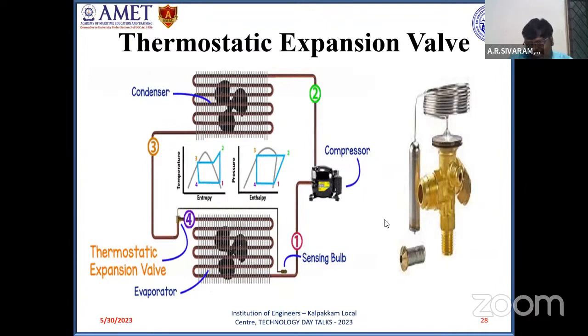Apart from this, it has a sensing bulb. Normally, the sensing bulb of the thermostatic expansion valve is situated at the evaporator outlet. The sensing bulb sees to it that the refrigerant always leaves the evaporator as a vapor, so that no liquid enters the compressor. In case liquid is leaving the evaporator, of course the accumulator will accumulate it. But apart from that, once there is a possibility of liquid refrigerant at the evaporator outlet, the thermostatic expansion valve reduces the mass flow rate of refrigerant accordingly.